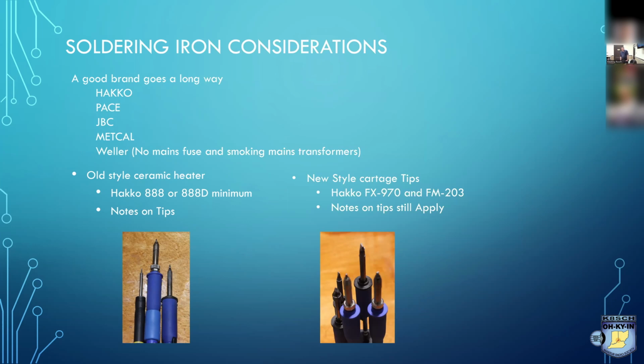Soldering irons, any good brand soldering iron, pick your brand. Hakko, Pace, JBC, Metcal. Weller does make the list. However, if you have one of the blue boxes from Weller, for whatever reason, they took the mains fuse out of the power transformer. So they have been known to burn up power transformers before. That typically happens less here than it does overseas, where they have 240 volt. But I don't know why they pulled the mains fuse out of the power transformer, but they did.